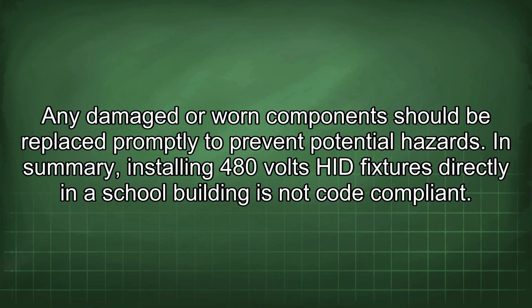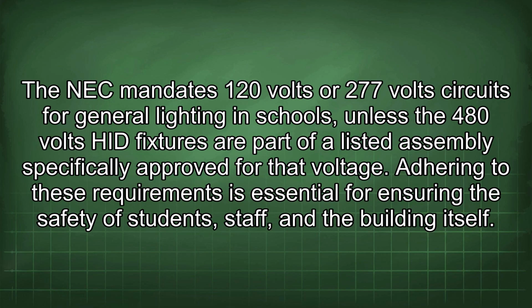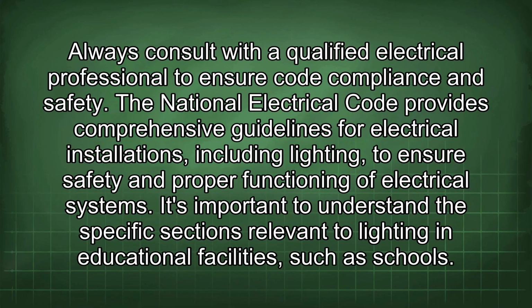In summary, installing 480-volt HID fixtures directly in a school building is not code compliant. The NEC mandates 120-volt or 277-volt circuits for general lighting in schools unless the 480-volt HID fixtures are part of a listed assembly specifically approved for that voltage. Adhering to these requirements is essential for ensuring the safety of students, staff, and the building itself. Always consult with a qualified electrical professional to ensure code compliance and safety.